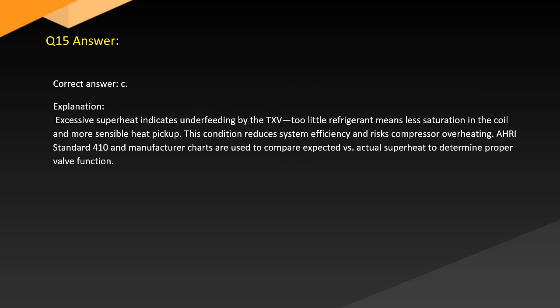Answer. Correct answer: C. Explanation. Excessive superheat indicates underfeeding by the TXV. Too little refrigerant means less saturation in the coil and more sensible heat pickup. This condition reduces system efficiency and risks compressor overheating. AHRI Standard 410 and manufacturer charts are used to compare expected versus actual superheat to determine proper valve function.